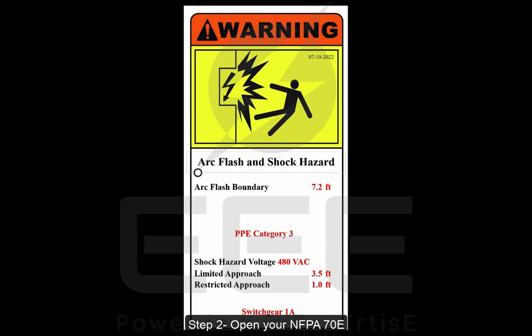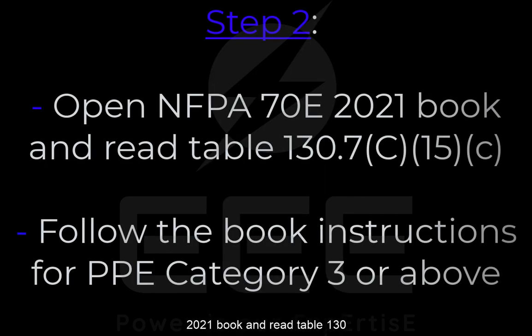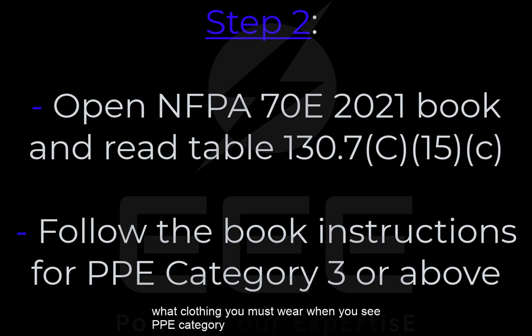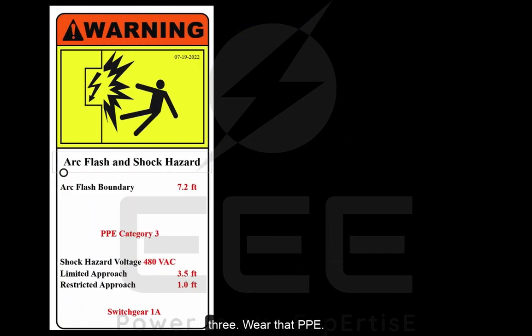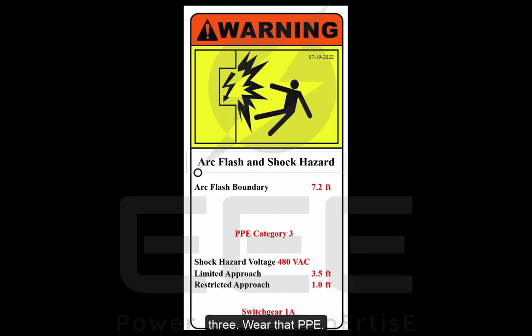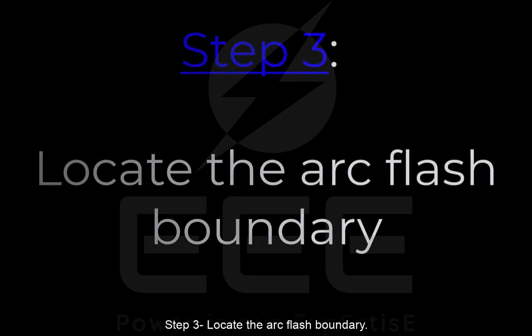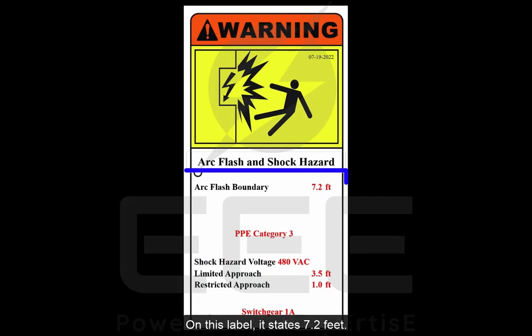Step 2. Open your NFPA 70E 2021 book and read Table 130.7C 15C. It clearly tells you, at the minimum, what clothing you must wear when you see PPE Category 3. Wear that PPE. Step 3. Locate the arc flash boundary. On this label, it states 7.2 feet.